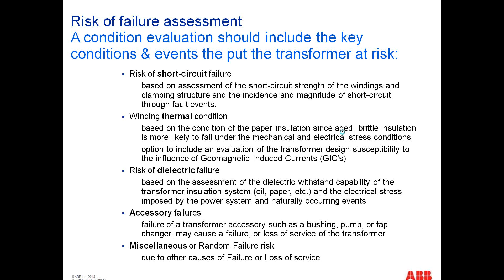Now, accessory failures, and Doble put out a few years ago that between bushings and tap changers, about 35% of transformer failures happen by accessories. So you can't forget that when you're doing a good, solid condition assessment. And then, of course, there are other system-based events, maybe relaying practices, maybe susceptibility to geomagnetic disturbances, sort of location or environmental events, whether you're in a tornado or hurricane-prone area, for example, that could damage the transformer. So you've got to look at all 5 of these things if you're going to have a solid condition assessment program.